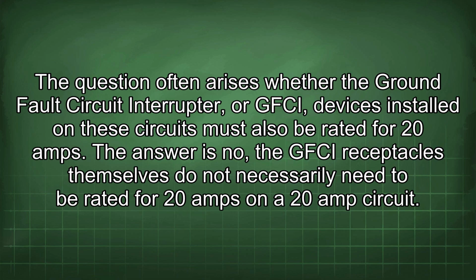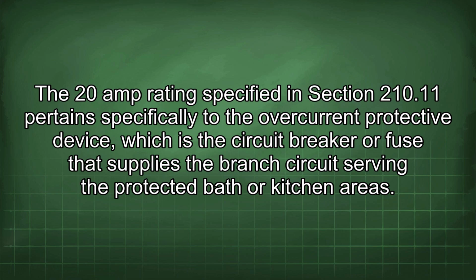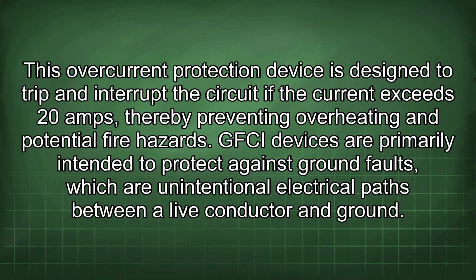The GFCI receptacles themselves do not necessarily need to be rated for 20 amps on a 20 amp circuit. The 20 amp rating specified in section 210.11 pertains specifically to the overcurrent protective device, which is the circuit breaker or fuse that supplies the branch circuit serving the protected bath or kitchen areas. This overcurrent protection device is designed to trip and interrupt the circuit if the current exceeds 20 amps, thereby preventing overheating and potential fire hazards.